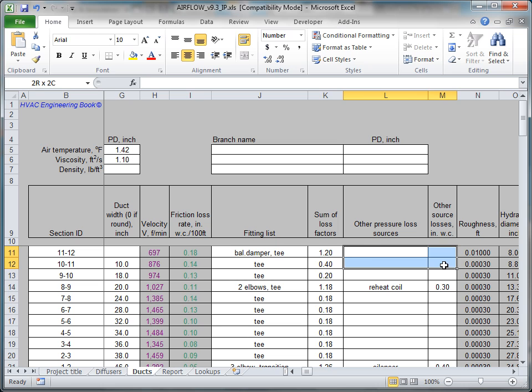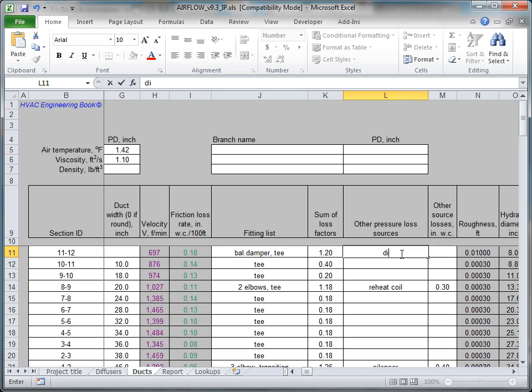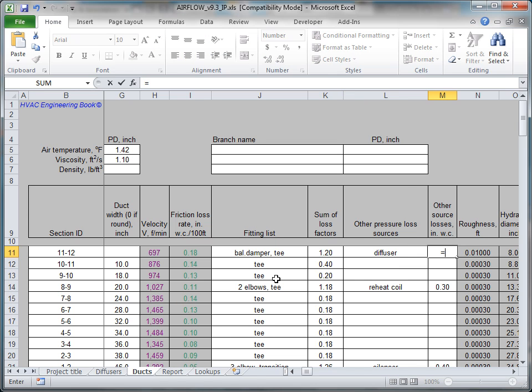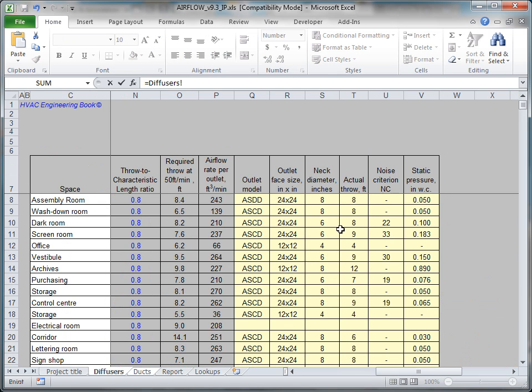Enter custom pressure drops into the next two columns. For example, section 11-12 contains a diffuser. Input the pressure loss across the diffuser found in the diffusers tab.